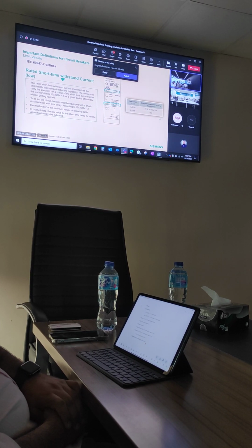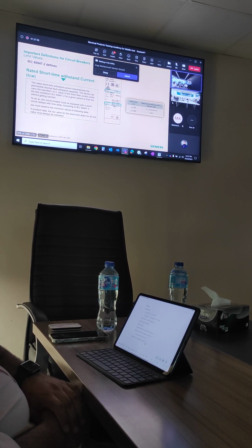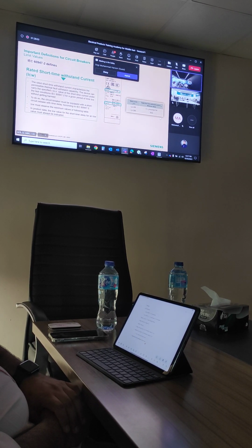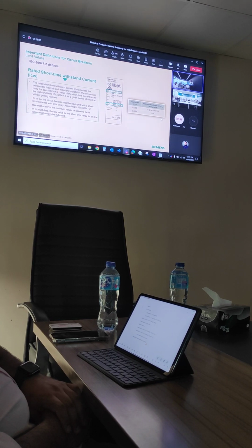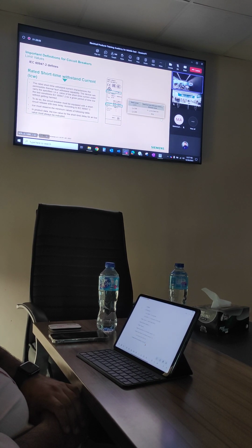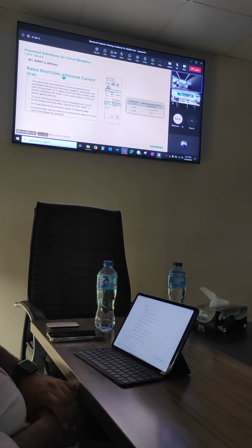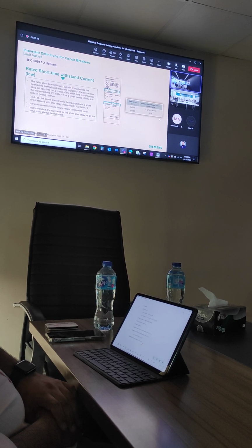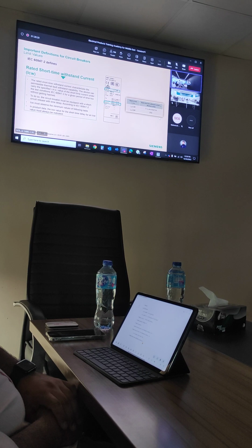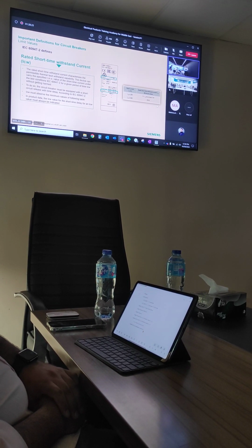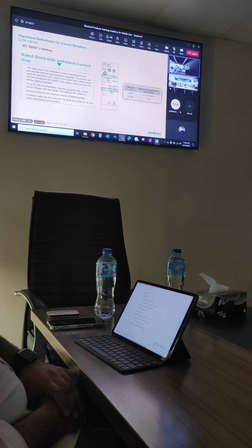I mean, when this short circuit is on the bus, the incoming device is supposed to monitor this short circuit and wait for any action, at least for 1 second, and allow the downstream devices which have instantaneous magnetic trips or short circuit releases to trip earlier. So the incoming device needs to have this withstand capability. So typically this withstand capability is seen with ACBs, air circuit breakers, and in very high rating molded case circuit breakers, which could be intended to work as an incomer.